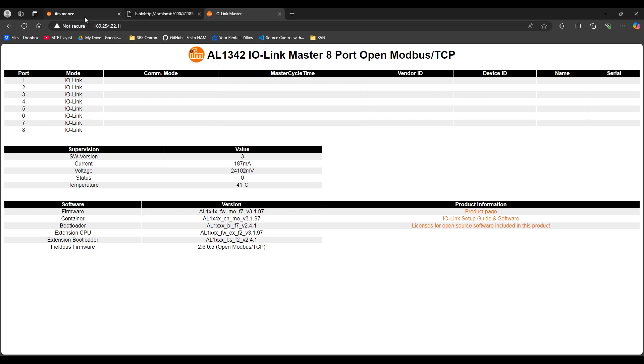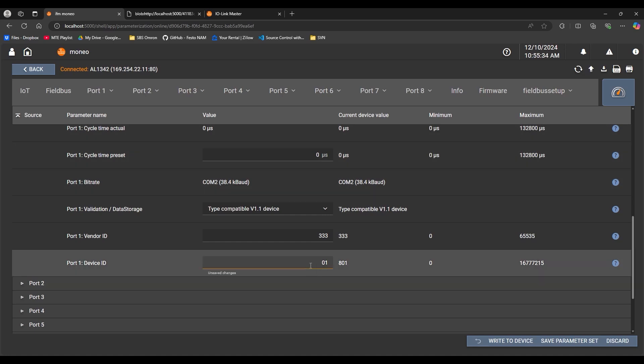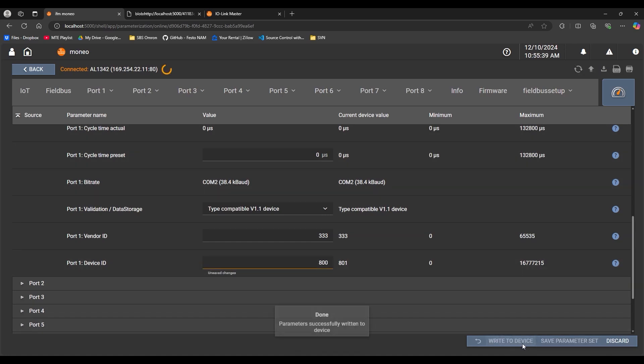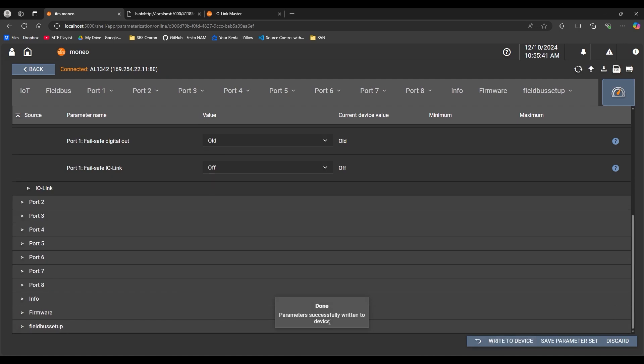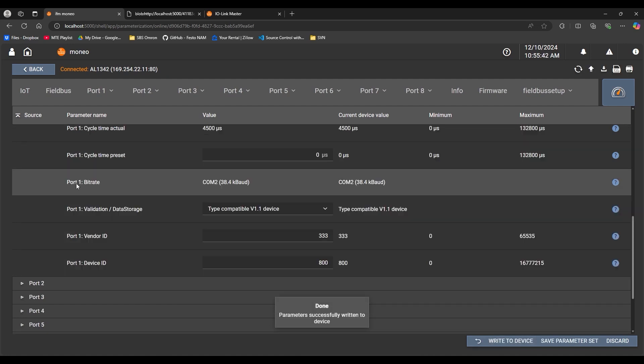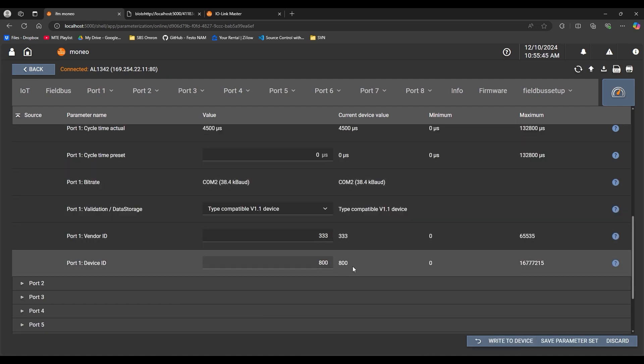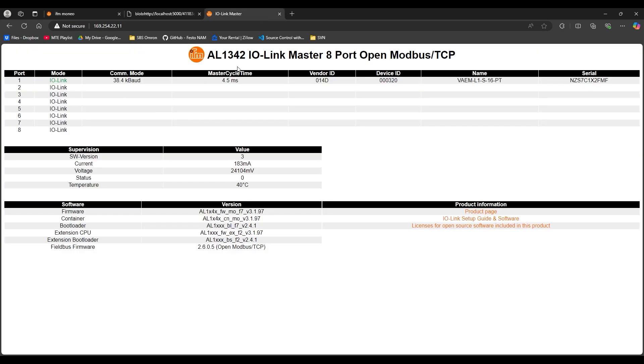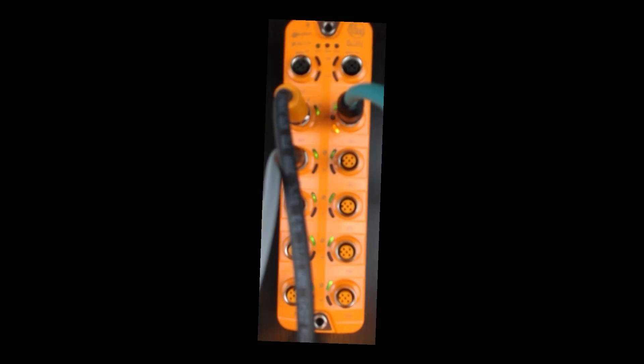If I go back to Moneo, and I change the device ID to the correct value, so 800, and we know this again from the IO-DD file, write it to the device, double-check that it was written, you can see that under current device value. Now I'll go back to that web server, and you can see that it's detecting the vendor ID, the device ID, and the device itself, and network communications to any kind of PLC would be successful. We can confirm this again by going back to look at our IO-Link master, and you can see now the light that was blinking red is now solid green, indicating a successful network connection or point-to-point connection for IO-Link.